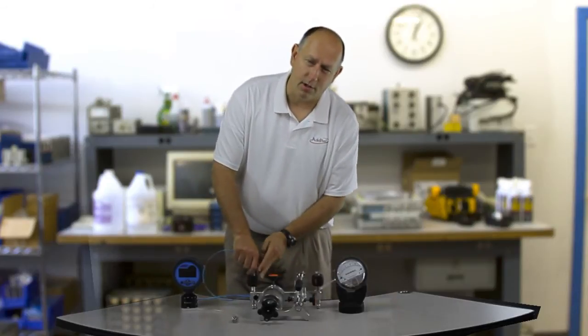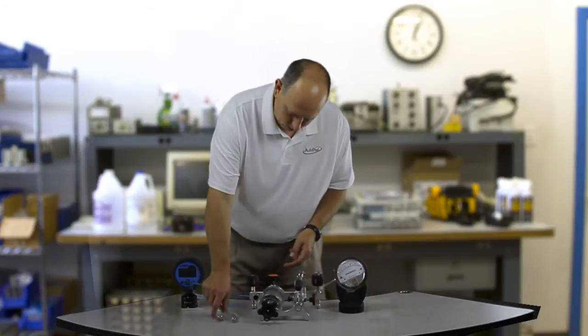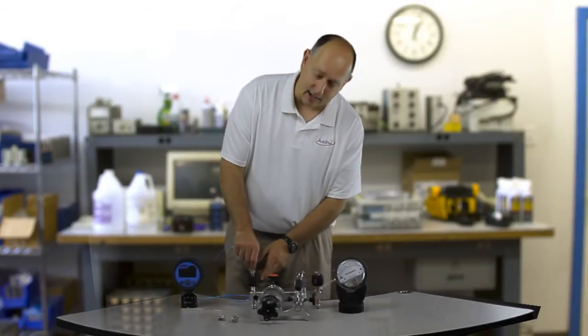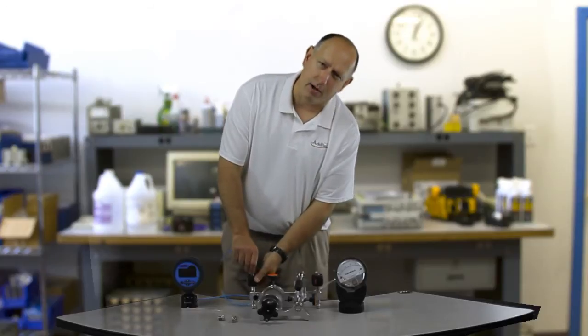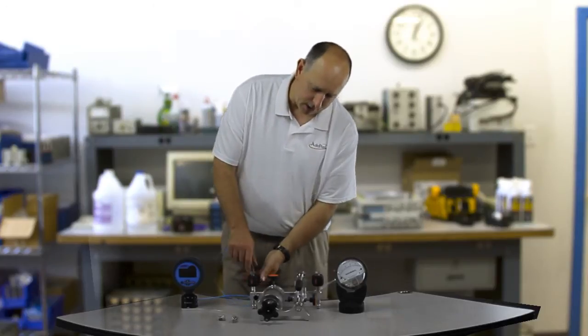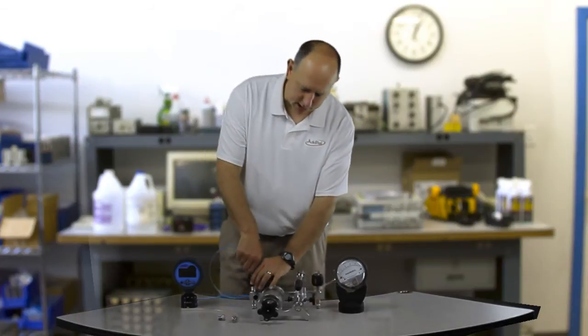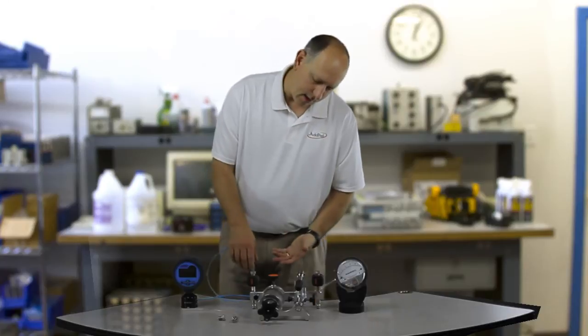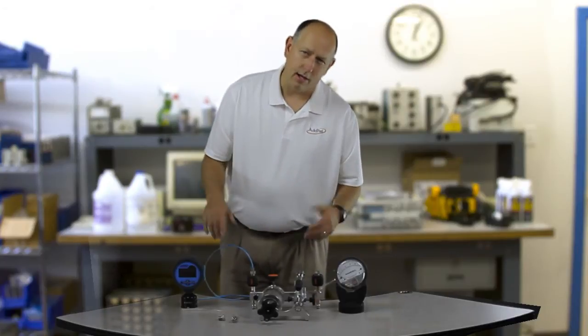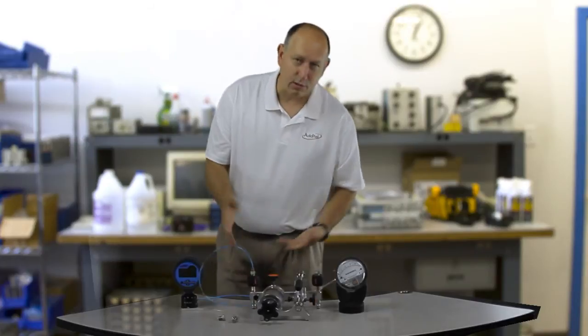Now I'm going to hook the high sides up to the pump — first the reference. One of the really nice things about Additel pumps are these quick disconnectors. I don't need to use tape. I don't need to use wrenches. I just put it in finger tight and screw it down. Lots of customers will really clamp down and screw it in tight, which will smash down the rubber O-ring and give you a shorter lifespan. If you just put these in finger tight, that's plenty good.